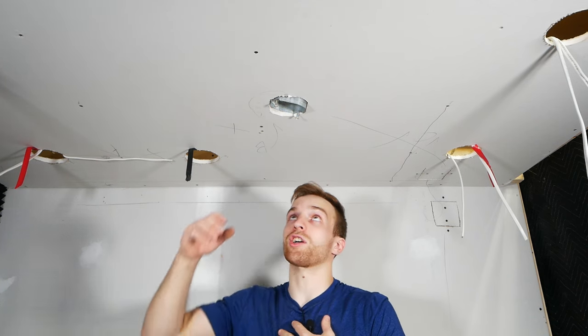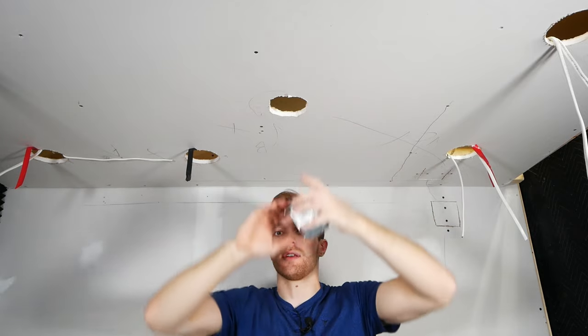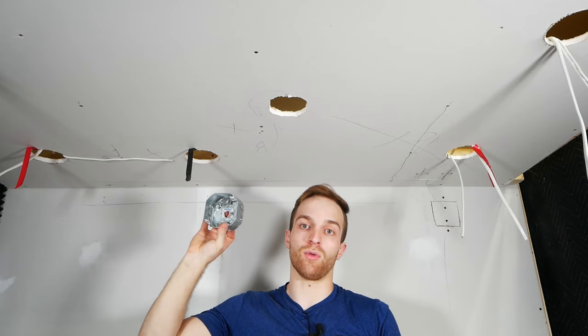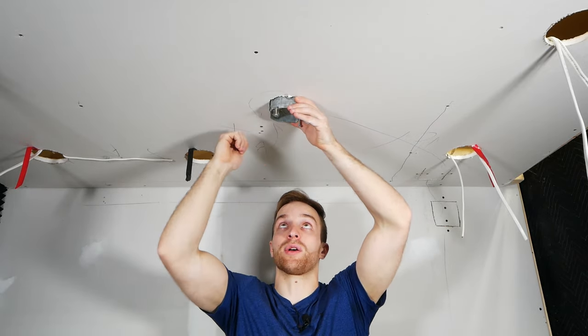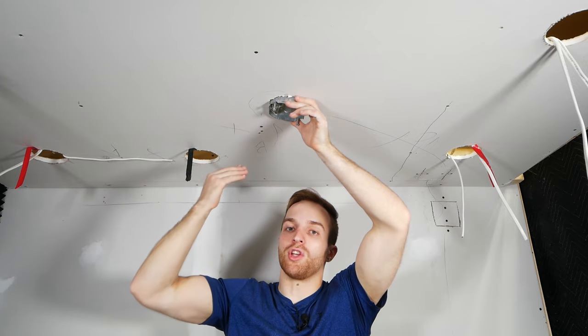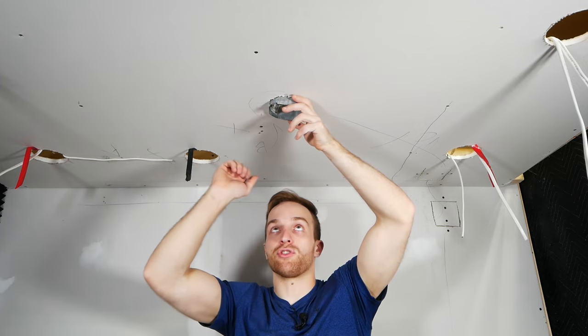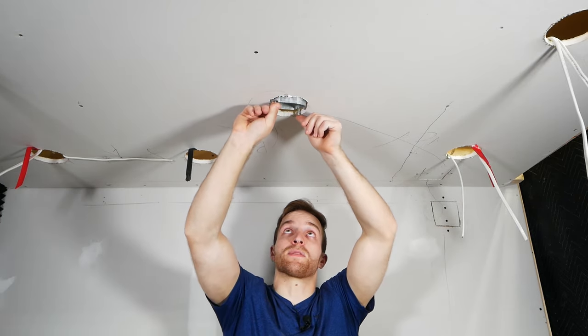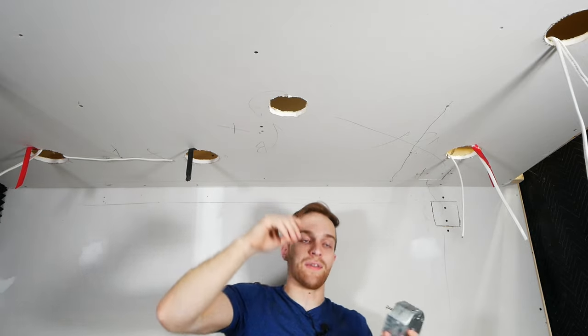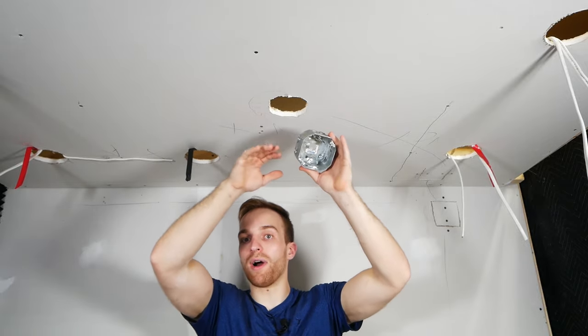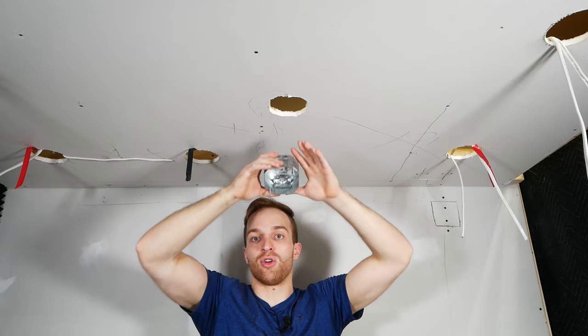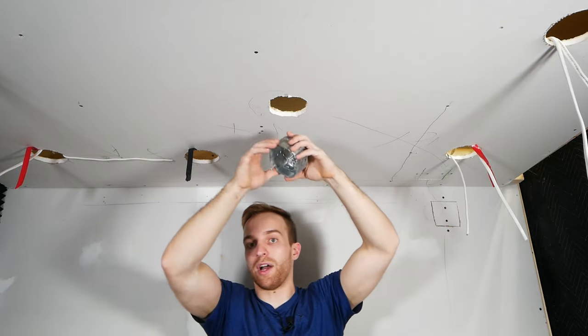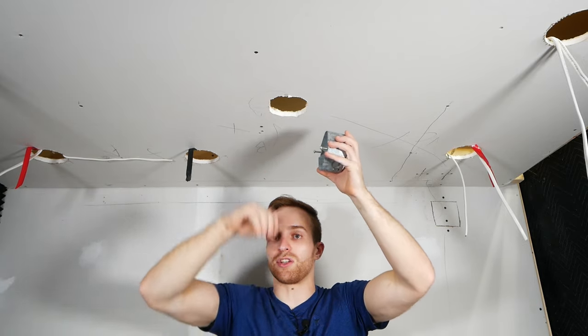I just want to take a quick second and talk about what do you do if you're in the scenario where you have a existing light and it has a box full of wires. So if you run into this, the important thing to note is that when you take out the light fixture that was here, make a note of which leads were connecting the light fixture to the box. It is most likely a black and a white wire and you're just going to want to take note of those two wires. The reason being is what we're going to do is you still want to try to get this box out if you can. It'll just make it a lot easier. And then you're going to have to run an additional wire from this box with all of the wires in it to one of your pot lights and that's going to act as your switch line.